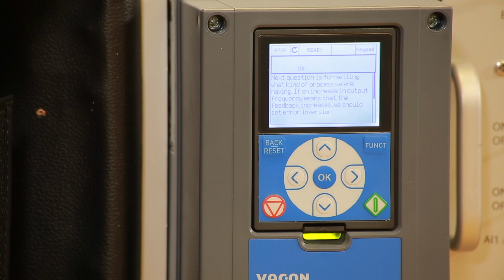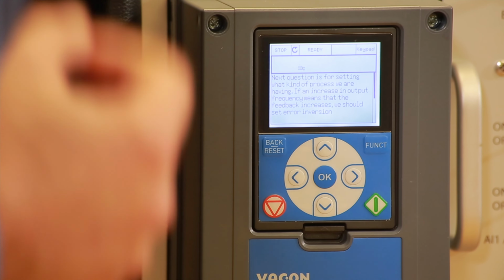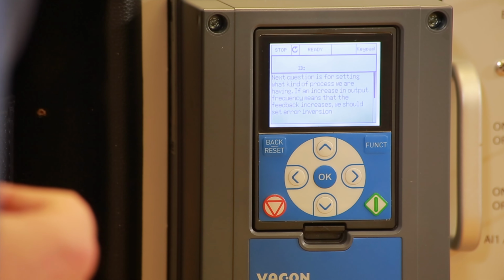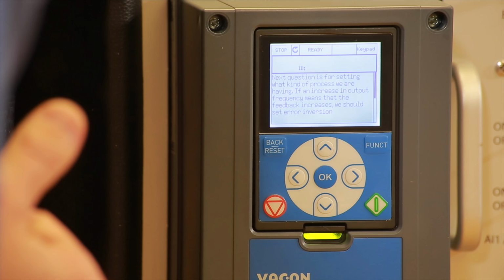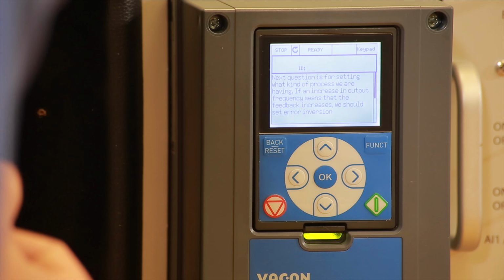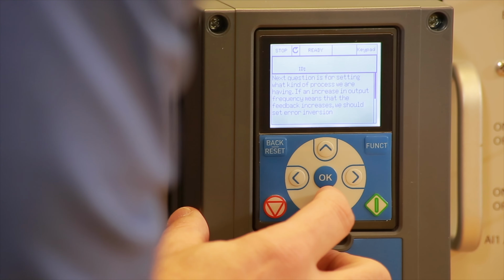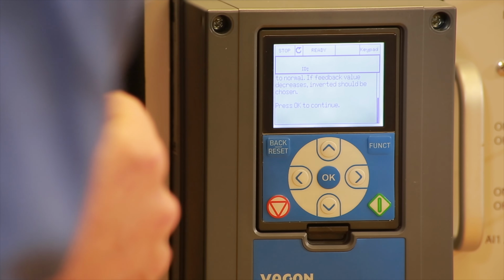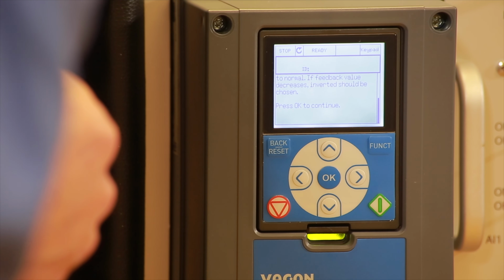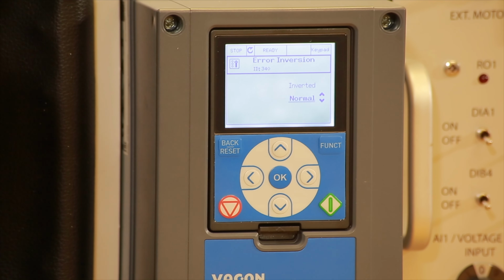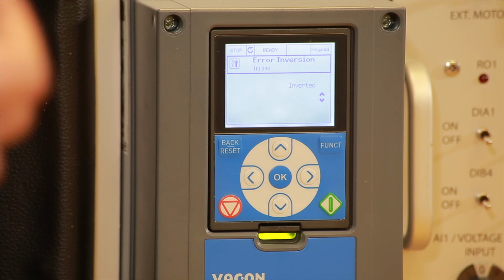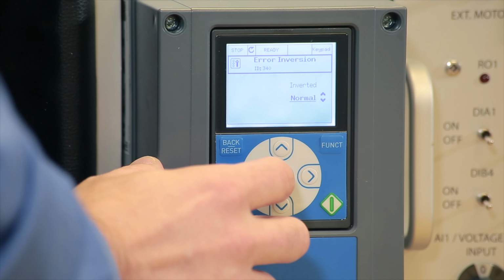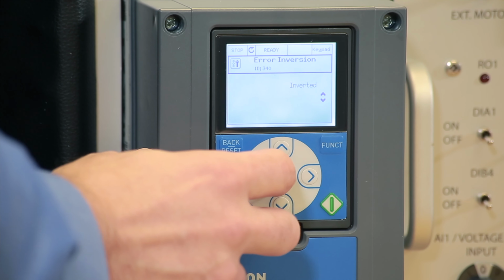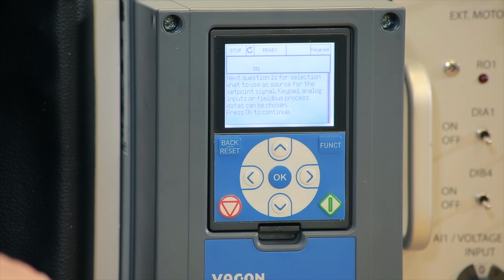Next, the drive guides us, and the next question is for setting what kind of process we're having. If an increase in output frequency means that the feedback increases, we should set error inversion to normal. If the feedback value decreases, inverted should be chosen. In my experience with three-phase power, we have always used normal. We'll just leave it at that. Inverted is very rare, not in our application. So for our case, normal is fine.